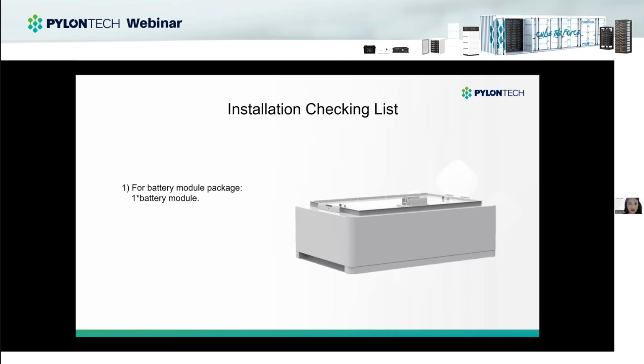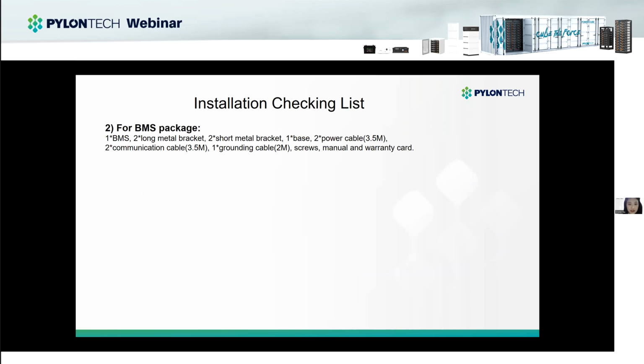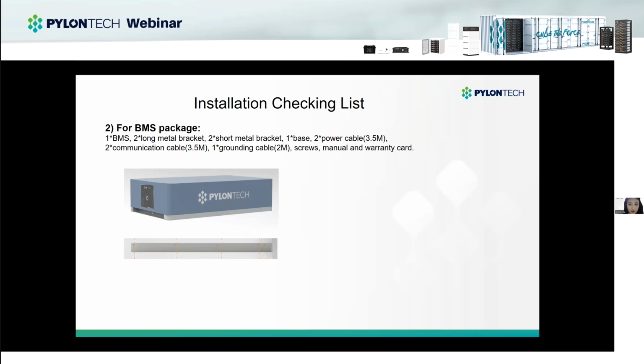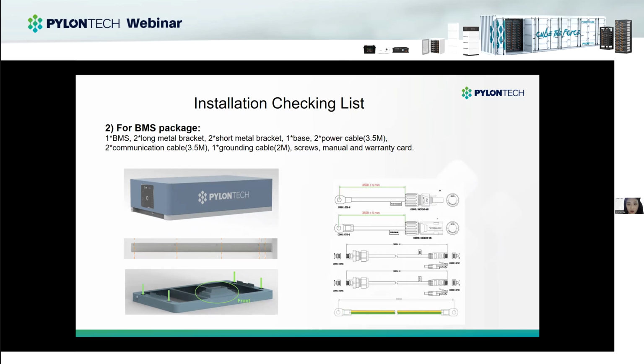Next part is the installation. When you purchase our battery modules, you will receive the number of battery modules you bought. And for the BMS package, you will receive 1 BMS, the brackets for stability, 1 base, a pair of power cables to connect the BMS to the inverter, and 2 communication cables. One is to connect the BMS to the inverter. The other is for backup use. And a grounding cable, the operation manual and the warranty card.